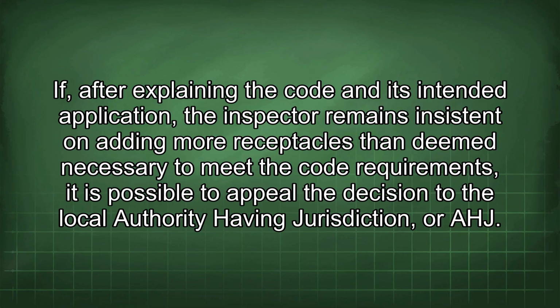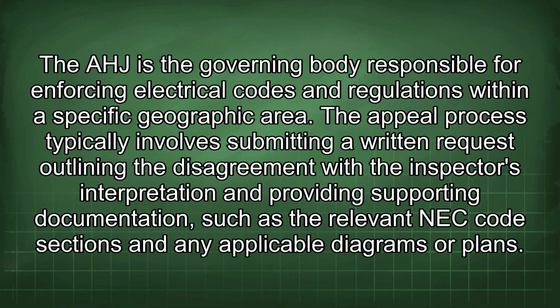If, after explaining the code and its intended application, the inspector remains insistent on adding more receptacles than deemed necessary to meet the code requirements, it is possible to appeal the decision to the local authority having jurisdiction, or AHJ. The AHJ is the governing body responsible for enforcing electrical codes and regulations within a specific geographic area. The appeal process typically involves submitting a written request outlining the disagreement with the inspector's interpretation and providing supporting documentation, such as the relevant NEC code sections and any applicable diagrams or plans.